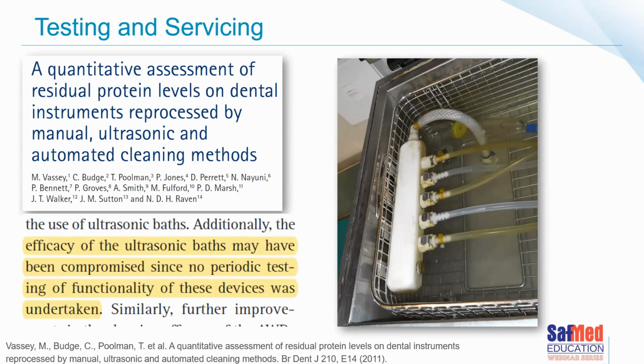There's an interesting paper published in a dental journal, in fact, looking at the efficacy of cleaning dental instruments manually or in an ultrasonic cleaner. I have to tell you that this particular paper was not nice to read, because it actually said in this particular incident that the manual cleaning method turned out to be better than the automated one, or the ultrasonic cleaner in this case. And the reason for that, as they clearly understood, was the fact that the efficacy of the ultrasonic baths had been compromised because they hadn't been tested periodically, and they indeed hadn't been serviced.